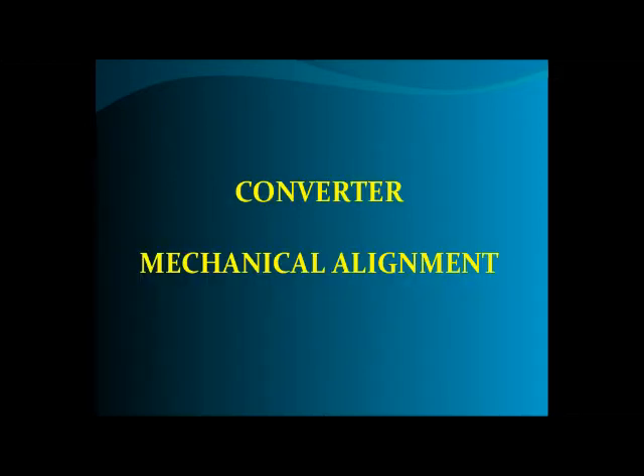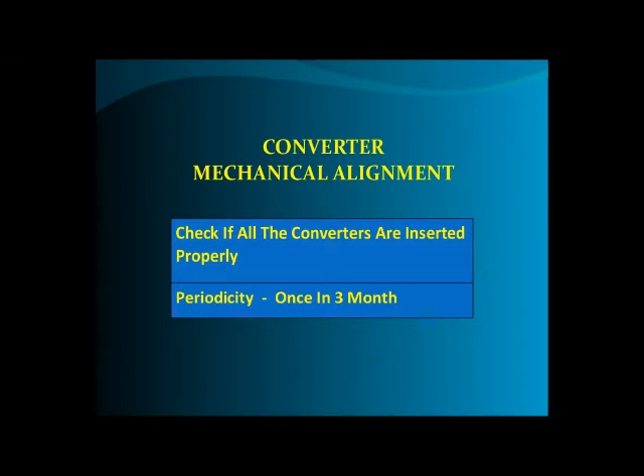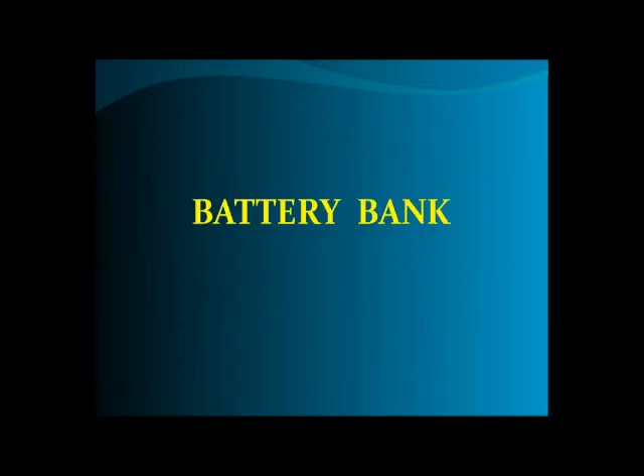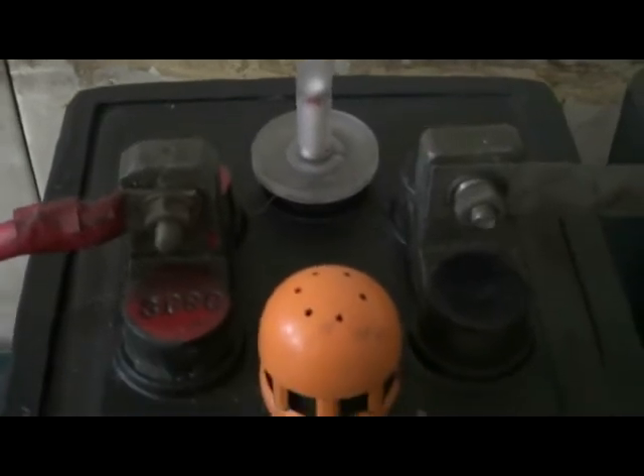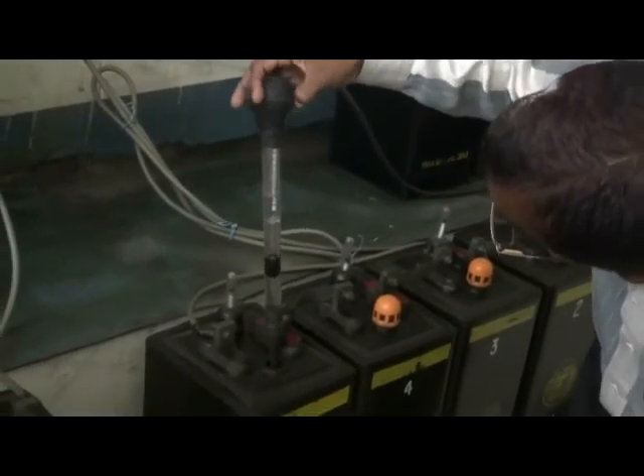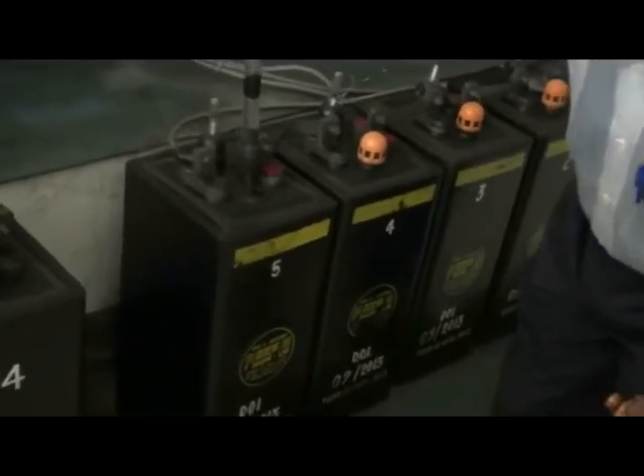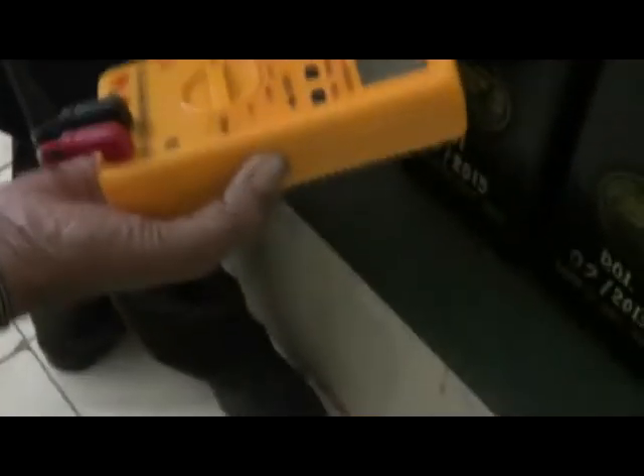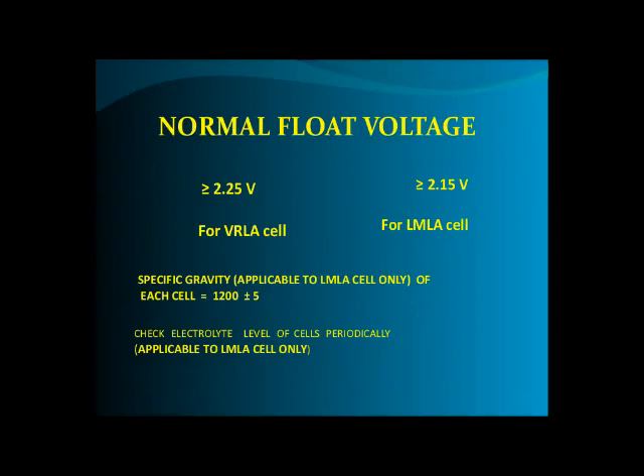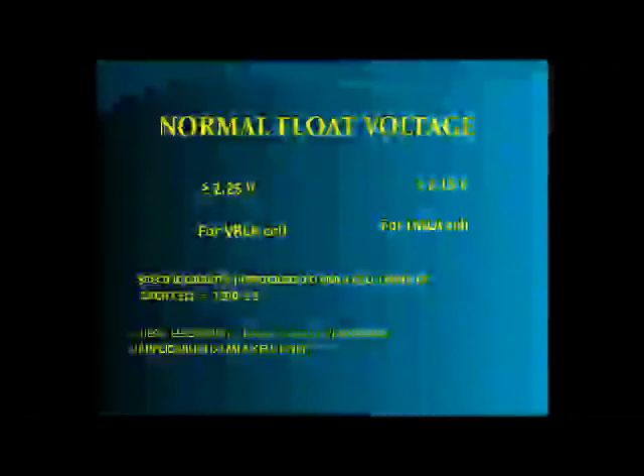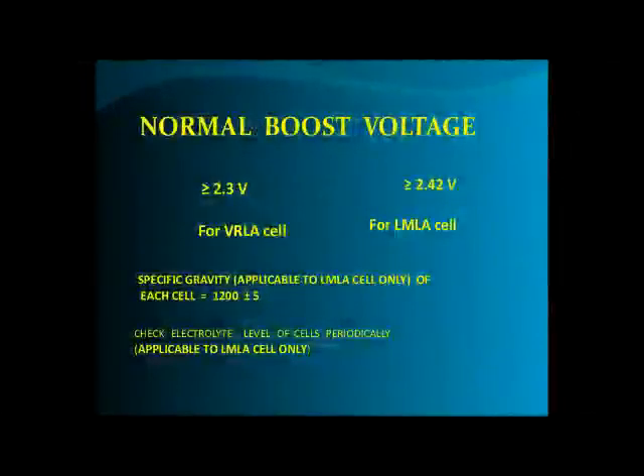Converter mechanical alignment: Check if all converters are inserted properly. Periodicity: once in 3 months. Battery bank: Check the batteries at regular intervals. Clean any sulfation found on battery terminals. Check specific gravity of each cell with a hydrometer — ideal value is 1200 ±5. Normal float voltage: 2.25V per cell for VRLA batteries and 2.15V per cell for conventional batteries. Normal boost voltage: 2.3V per cell for VRLA and 2.42V per cell for conventional batteries.